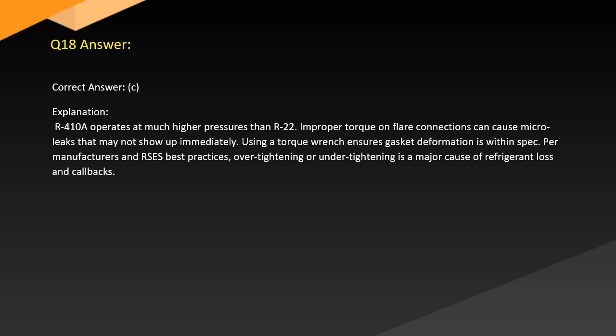Answer. Correct answer: C. Explanation. R410A operates at much higher pressures than R22. Improper torque on flare connections can cause microleaks that may not show up immediately. Using a torque wrench ensures gasket deformation is within spec. Per manufacturers and RSES best practices, over-tightening or under-tightening is a major cause of refrigerant loss and callbacks.